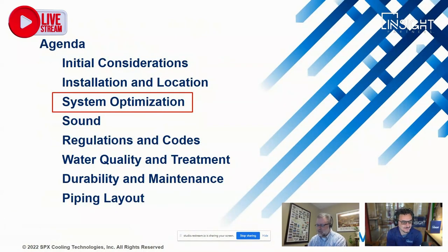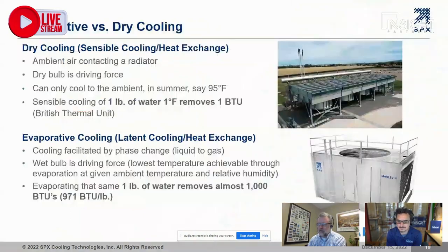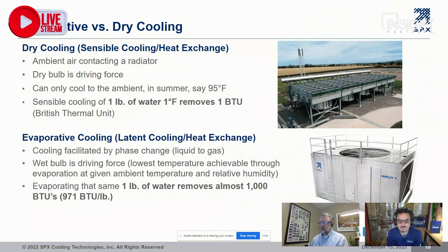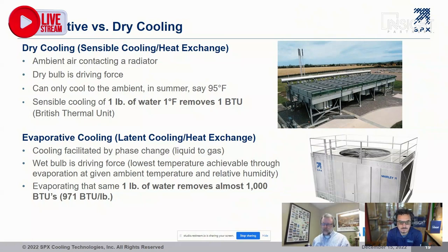From a system optimization standpoint, a common question is why use evaporative cooling versus dry cooling. Dry cooling is simpler — no water to deal with, no freezing, no water treatment — but the energy efficiency takes a huge hit. The key difference is that dry cooling is sensible cooling only: if you have one pound of water and cool it one degree Fahrenheit, you remove one BTU. But if you take that same pound of water and evaporate it, you remove almost 1,000 BTUs. Evaporative cooling's heat rejection capability is dramatically larger.